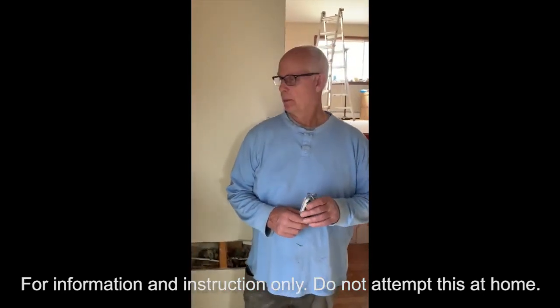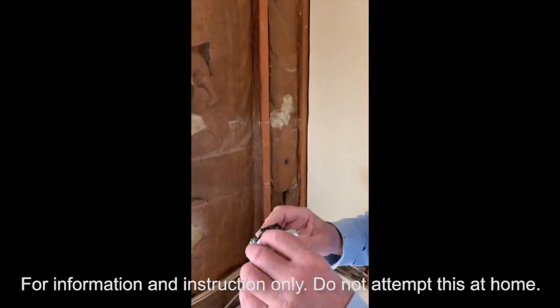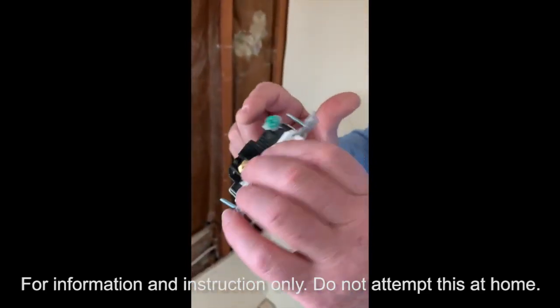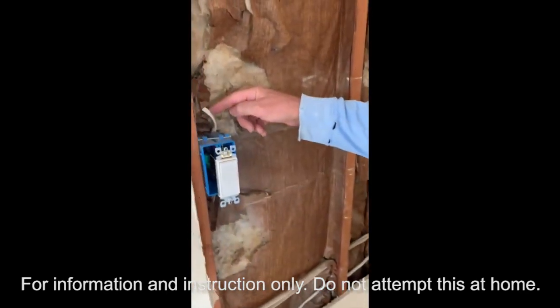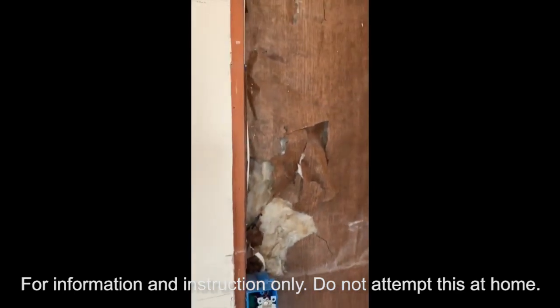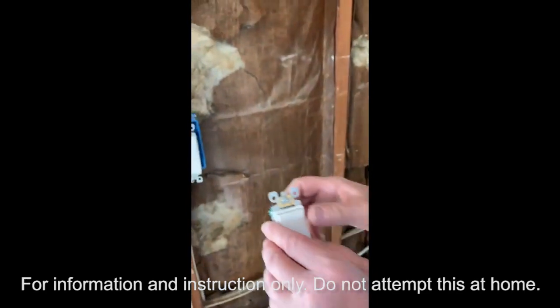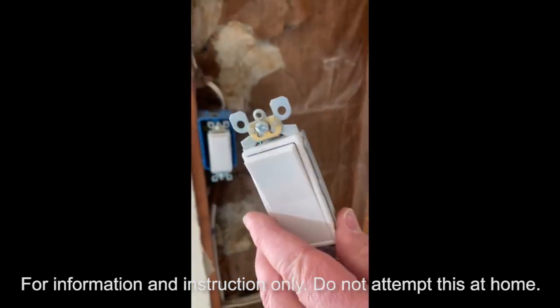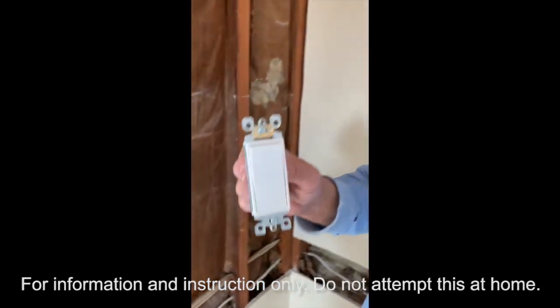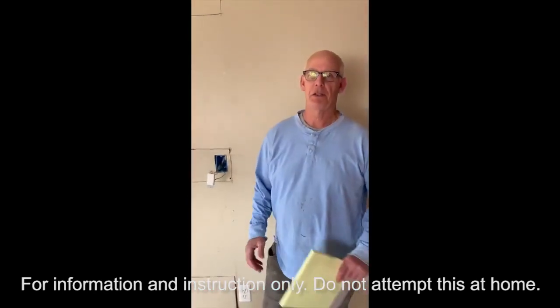Here's the second three-way switch — it's wired differently from the first. It has two brass screws for your two travelers, but the black screw is for your 14/2 black wire that goes from the box to the fixture. Make sure you put the 14/2 hot wire on the black terminal or it won't work correctly. The two travelers go on either side of the switch, and the green is for your ground screw.